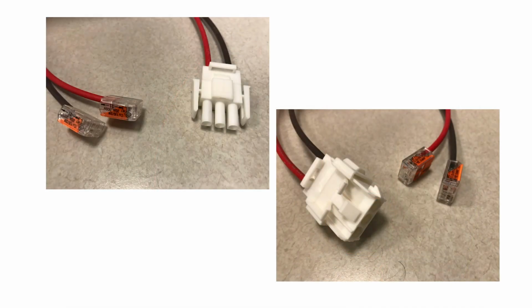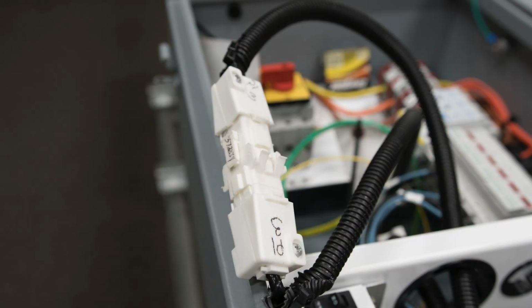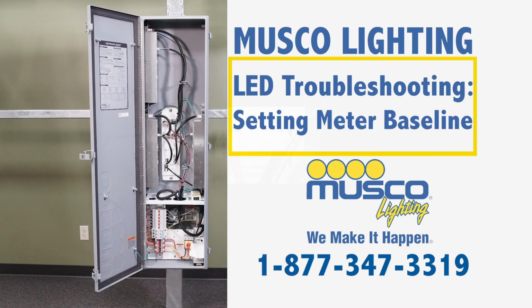If no controller is in the enclosure, use the MUSCO supplied 3-pin test harness and connect it to the output harness at the driver. If you do not have a MUSCO test harness, move to either the enclosure to pole harness connection or the output harness at the controller and use your meter probes to test. Please work with the MUSCO technical specialist to determine the correct procedure.